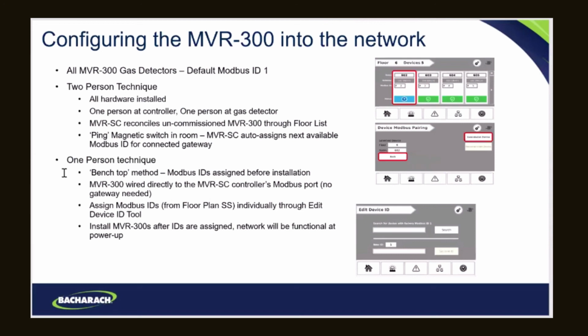Now, there's also a one-person technique, and it gets through the same thing, only the hardware is not commissioned yet. You still have to complete the CSV file. You still have to upload that to the controller, but what you're going to do, and this is a reason why that auxiliary Modbus port is in the controller, is connect your MVR 300 to that Modbus port in the controller, and it should still be able to walk through that.